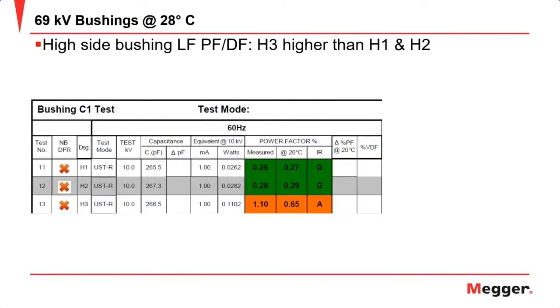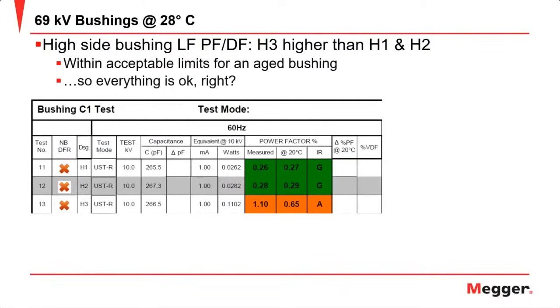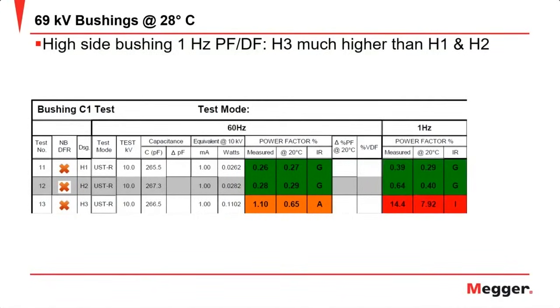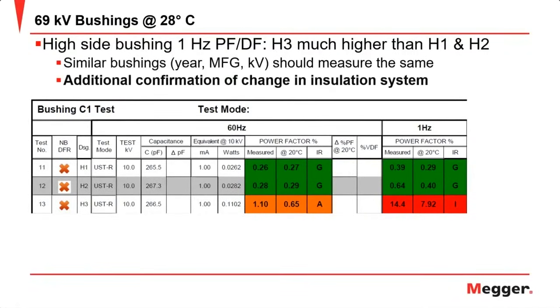But what the customer was able to do is also perform the test at 1 hertz. And what they saw was 2 things. The first being that the 2 bushings that measured good at 60 hertz were also measuring good at 1 hertz. So the 1 hertz, without trending, without having to have a database, confirmed that those first 2 bushings were in fact in good condition. The next thing that they saw was that the 3rd bushing clearly indicated a change in the insulation system for that H3 bushing, and those losses that were seen at 60 hertz were amplified down at 1 hertz. So 1 hertz enabled this particular customer to determine that 2 of the bushings were good, confirmed that they were good with 1 hertz, and then found that the 1 bushing was bad, and then confirmed with this extremely high 1 hertz power factor value.